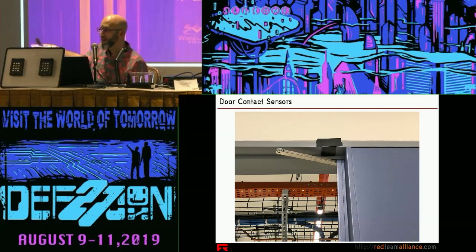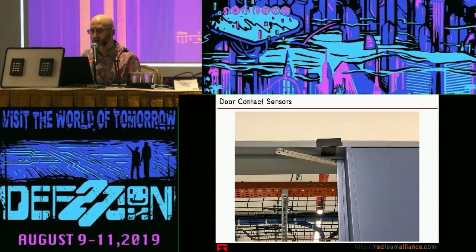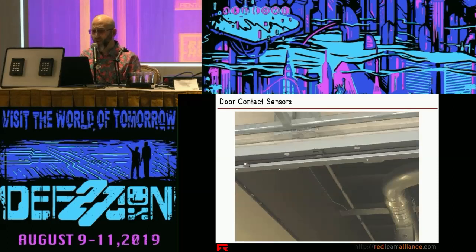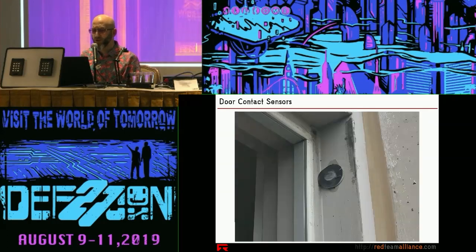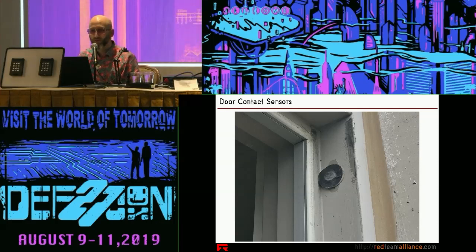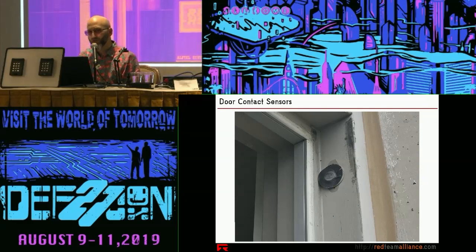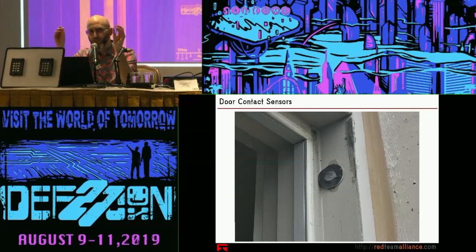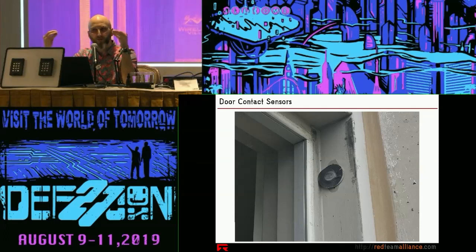The easiest, dumbest way to bypass a door contact is with a magnet. We were overseas without a lot of fancy tools, so I just took my hotel key card, bent it at 90 degrees to create a little shelf, taped a magnet to it, and shoved it in the door. That was enough to bypass the sensor, and the door into the data hall opened. But according to the access control system — the door is still closed. We taped our magnet in a circular shape, so the average user wouldn't notice. These are the small details about modern access control systems, beyond RFID, that you want to be aware of.